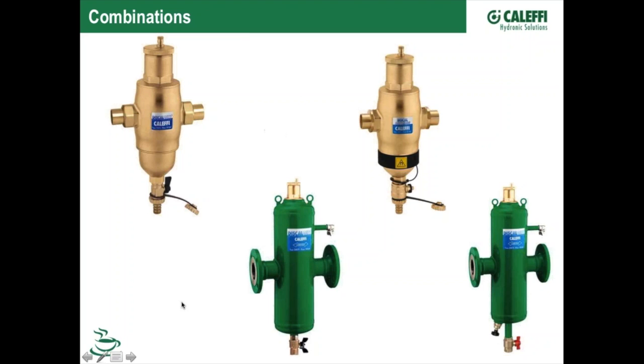My suggestion would be it would maybe depend on the type of system. If you've got a brand new system, it's all brand new copper pipe, new PEX tubing, you don't have a lot of rust and scale and debris from, say, maybe an old iron pipe or a cast iron radiator system, I'd like the air removal is probably most important to me. I'd probably put it up at the top on the hottest point in the system. Maybe if the system is an old iron pipe system and you're concerned with the flaking, the scaling being ongoing, I could put this down at the return. I can get air out of my system at the return. I'm going to do a better job at the top, at the hottest point, but I can also get air at the return. And the same thing with the dirt. I just would rather catch the dirt before it takes a trip or 2 through the boiler, through the heat exchanger.